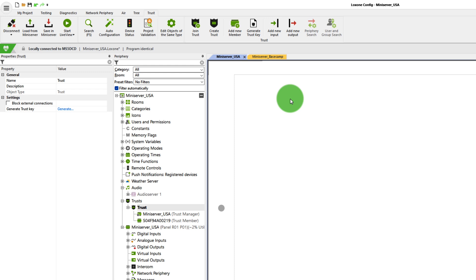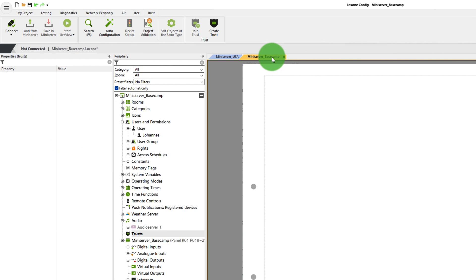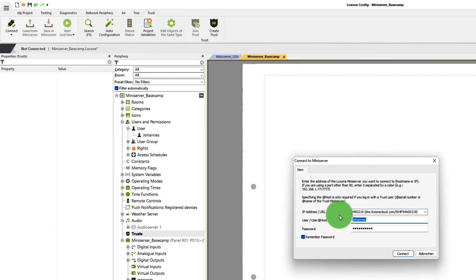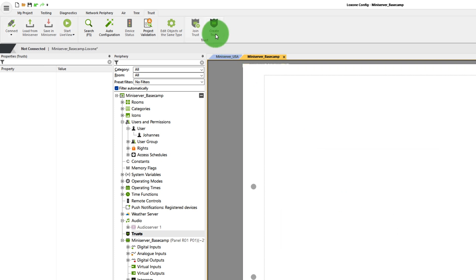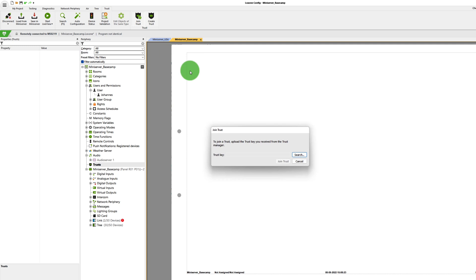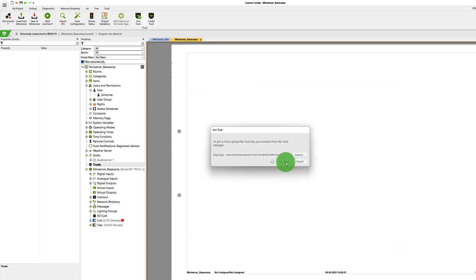Before we can switch to our Trust participant, the configuration has to be saved in the mini-server. Now, let's connect to the Trust participant, which in my example is the Basecamp mini-server, and this mini-server has yet to join the Trust. So to do this, click on Trust in the peripherals tree and then on Join Trust and open the file you created earlier. Afterwards, the connection is checked and the mini-server joins the Trust. Finally, this program as well must be saved into the mini-server. That way, additional mini-servers can be added to the Trust if they are created on the Trust manager beforehand.